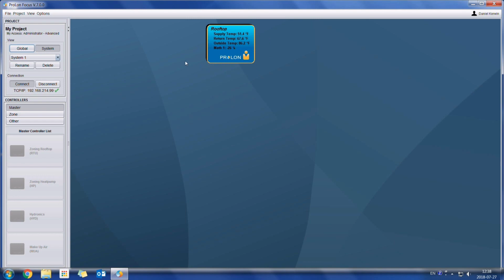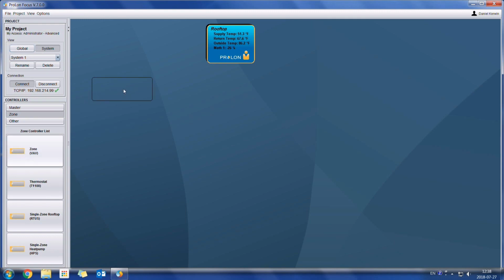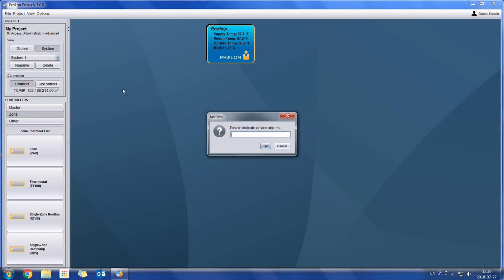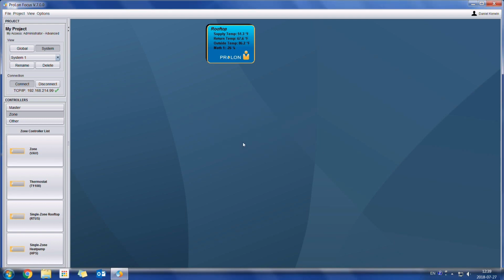Already we have a bit of information pop up. We can see what the temperature in the supply is, what the return temp, and the outside air temperature. Now, I also have some VAV zones which I would like to add. So I could simply click on the zone segment and drag and drop a zone controller like this. And so if my zone controllers have already been addressed, well then I could add them one by one in this way. However, we have a quicker way and more efficient way of doing this.